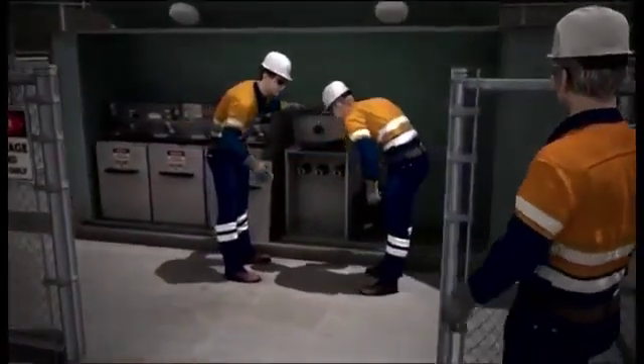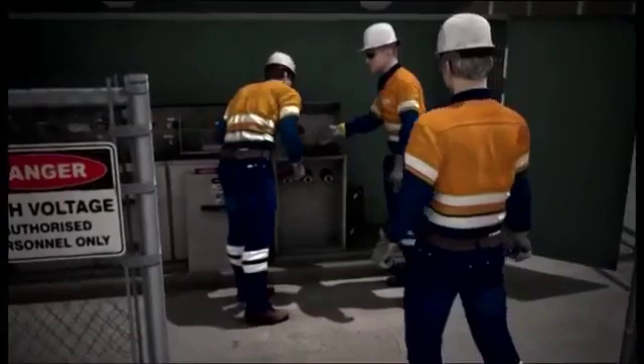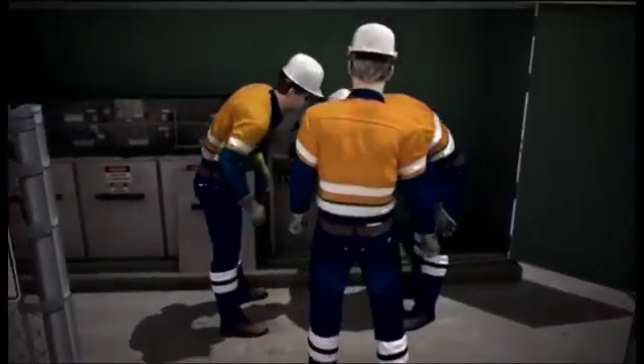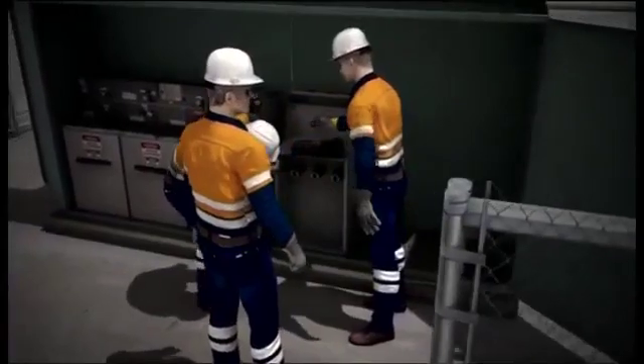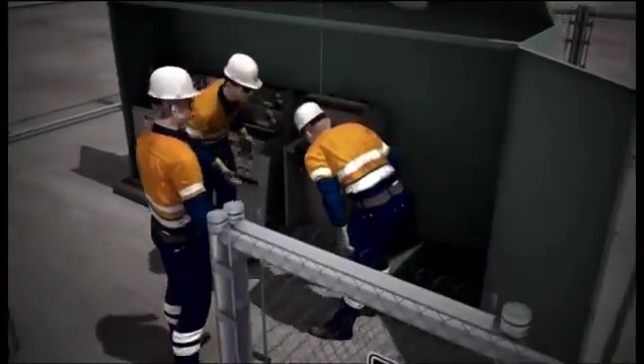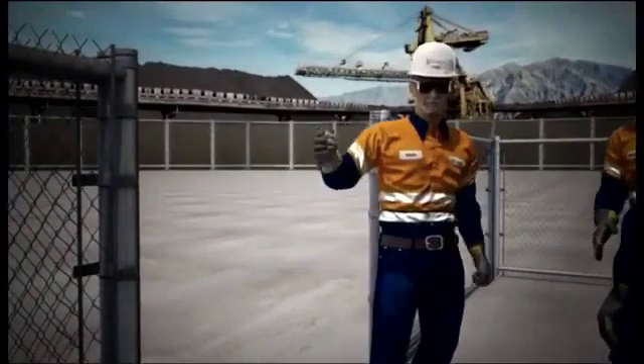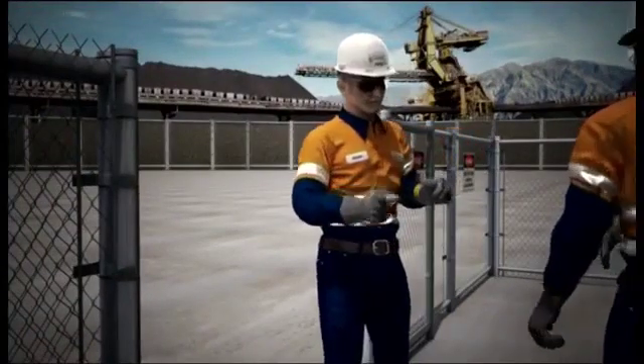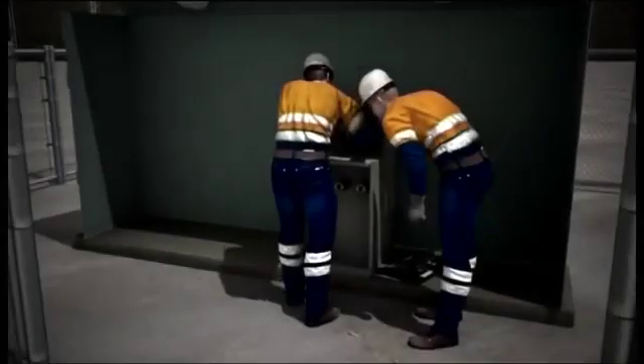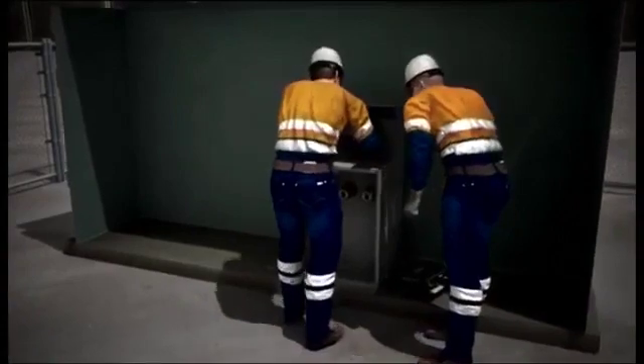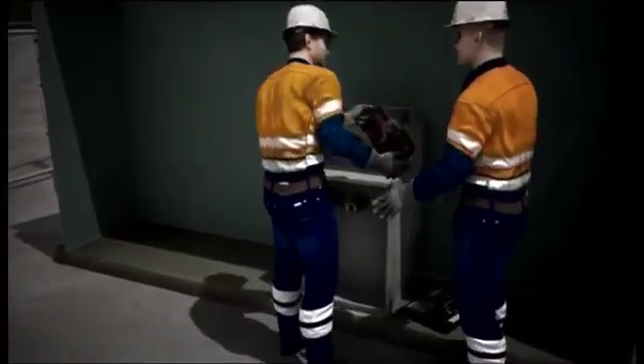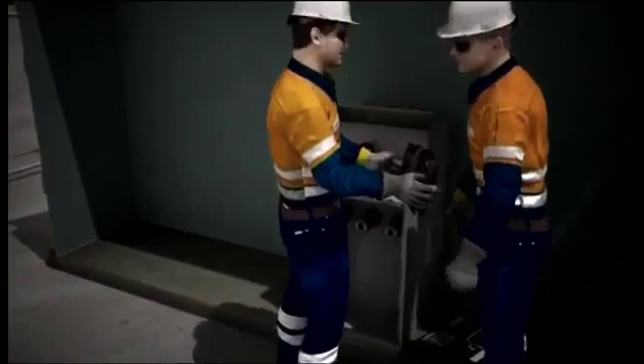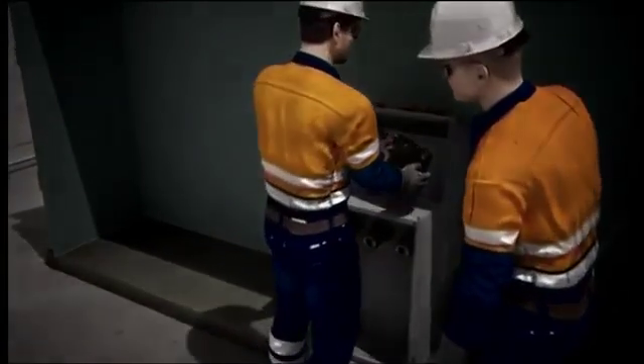By the time the supervisor returns, Dave and Andrew have successfully removed the faulty mechanism. They inspect the mechanism and discover that it has a broken spring and is too badly damaged to be repaired. The supervisor instructs them to remove an identical switch mechanism from a spare unit at a nearby distribution point. However, in removing this spare mechanism, the actuating springs inside the unit lost tension, making the switch unusable as a replacement. Every effort to recompress the springs in the workshop was unsuccessful.